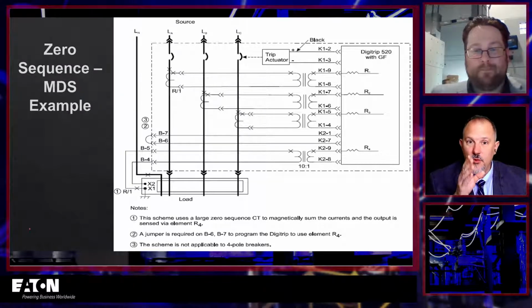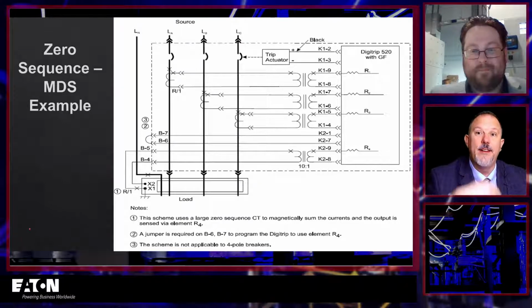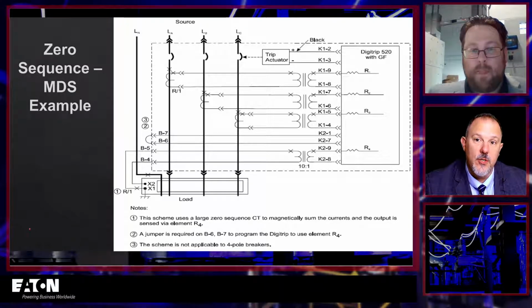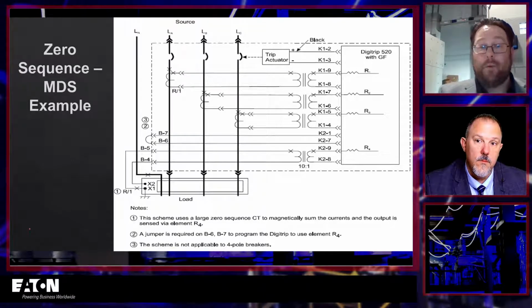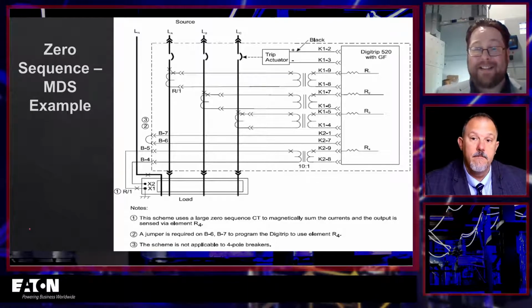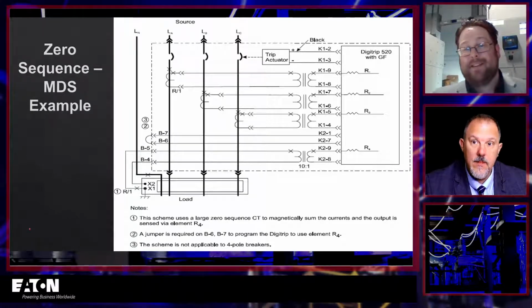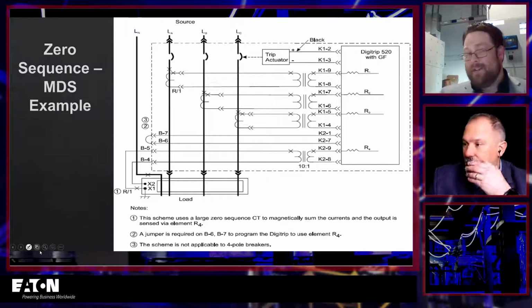But you make a very good point, and a very interesting point, that we need to put enough current through here to operate, so that these devices get their power and can actually function and do what they're supposed to do in the test sequence. Right. Because in the test sequence we're only injecting one phase, right? So we don't have all three CTs adding together to give us that power. That's a very good point.